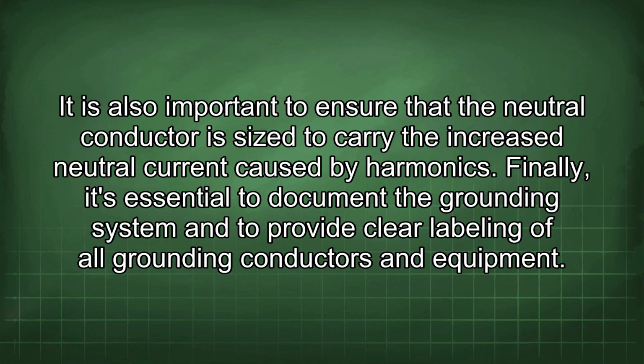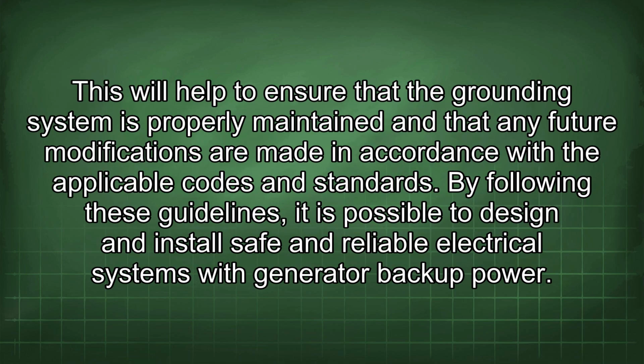It is also important to ensure that the neutral conductor is sized to carry the increased neutral current caused by harmonics. Finally, it's essential to document the grounding system and to provide clear labeling of all grounding conductors and equipment. This will help to ensure that the grounding system is properly maintained and that any future modifications are made in accordance with the applicable codes and standards. By following these guidelines, it is possible to design and install safe and reliable electrical systems with generator backup power.